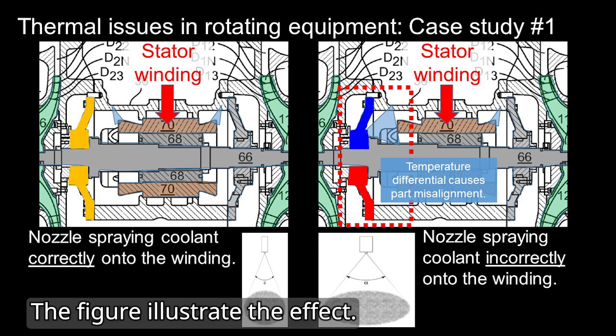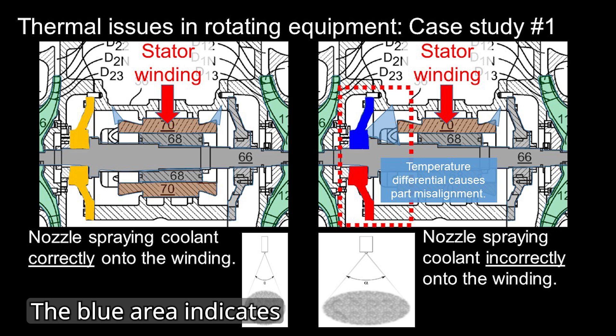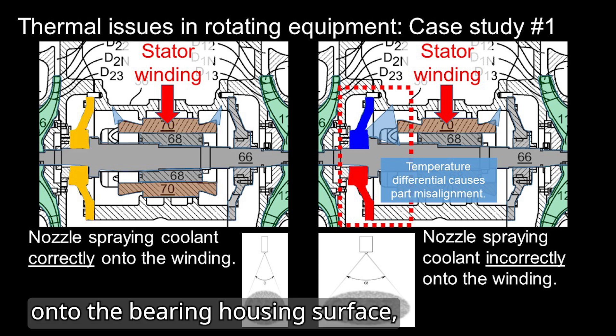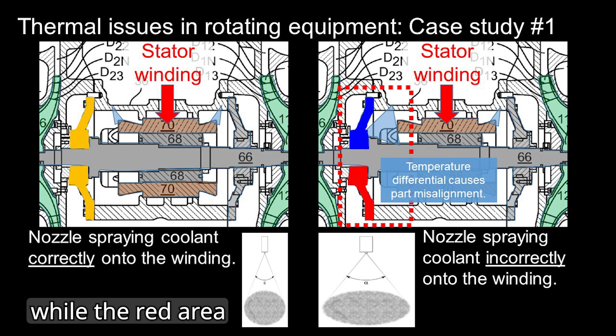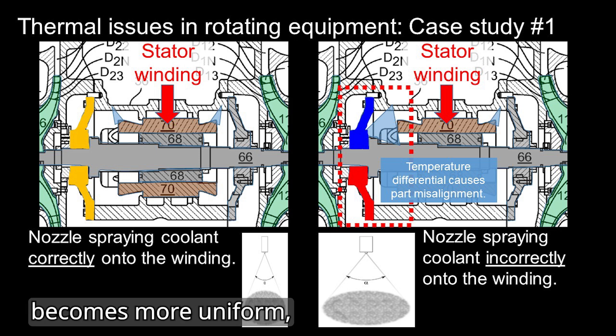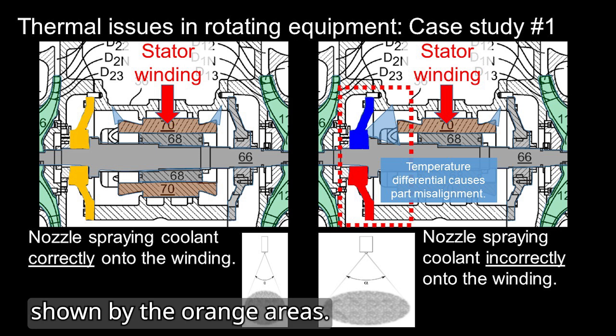The figure illustrates the effect. The blue area indicates cooling from the nozzle spraying liquid onto the bearing housing surface, while the red area represents hotter regions. With the nozzle properly aligned to the motor winding, the bearing housing temperature becomes more uniform, shown by the orange areas.